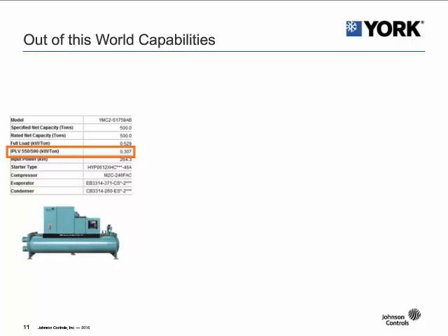Are there any consequences in operation or efficiency when the chilled water side is a lower temperature, i.e. using this system to build ice for storage systems? Sure. I can talk generally about that. So generally, when we refer to a 1 degree reduction in the evaporator temperature, so I go from 44 degree leaving chilled to 43 degrees leaving chilled, that typically has an impact to the chiller efficiency of about 2 to 2.5% on the efficiency of the chiller.